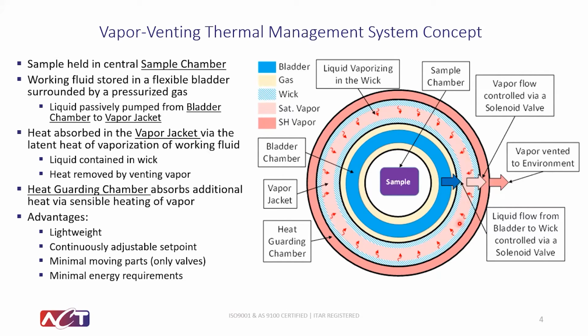At a predetermined set point, a second valve can be opened, venting vapor from the vapor jacket and reducing the temperature. The vapor can then flow through the final chamber, known as the heat guarding chamber, to absorb additional thermal energy as sensible heating before the vapor finally vents to the environment.